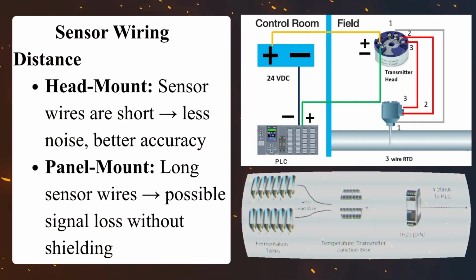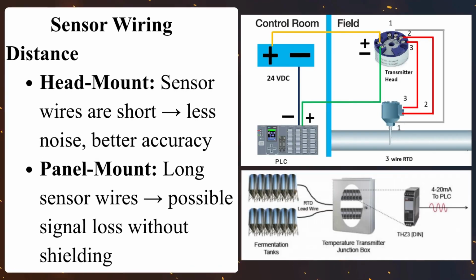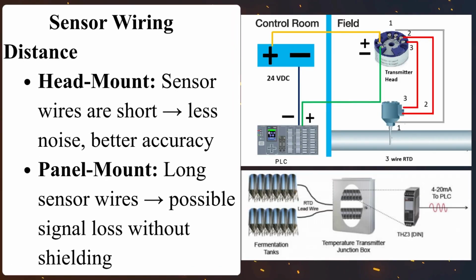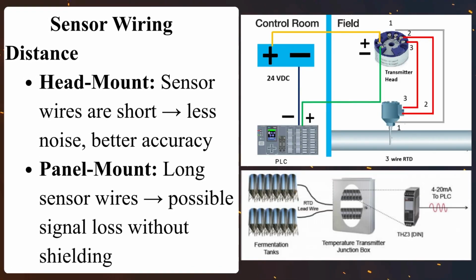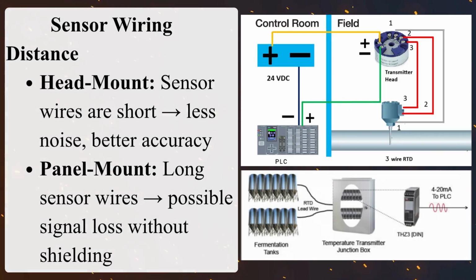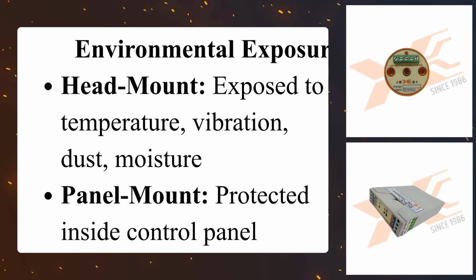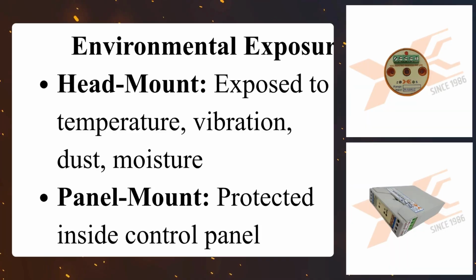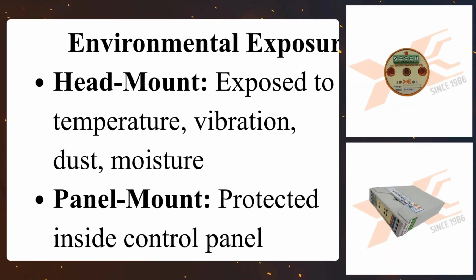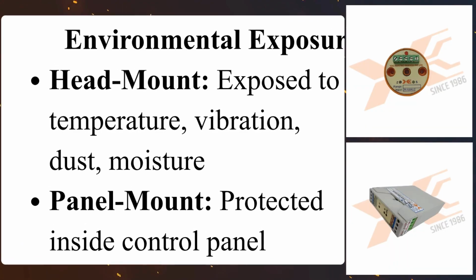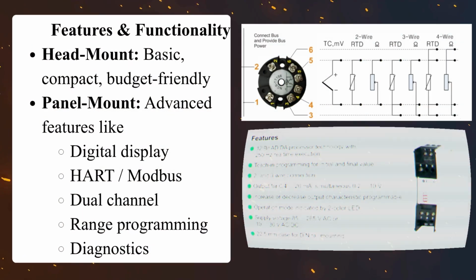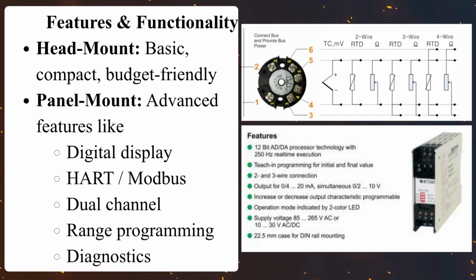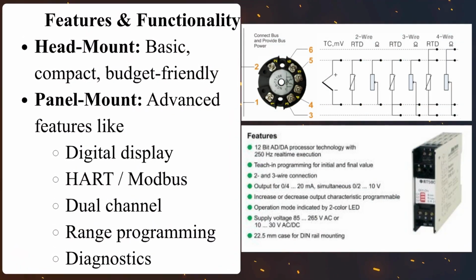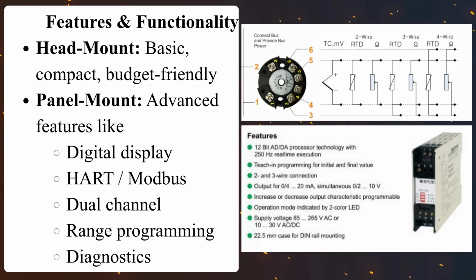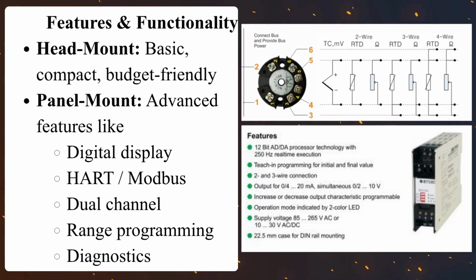2. Sensor wiring distance. Head mount: sensor wires are short, less noise, better accuracy. Panel mount: long sensor wires, possible signal loss without shielding. 3. Environmental exposure. Head mount: exposed to temperature, vibration, dust, moisture. Panel mount: protected inside control panel. 4. Features and functionality. Head mount: basic, compact, budget-friendly. Panel mount: advanced features like digital display, HART, Modbus, dual channel, range programming, diagnostics.